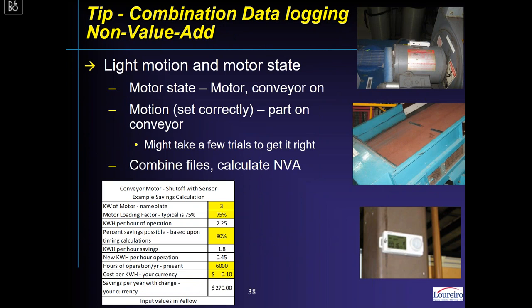One of the things we like to do is combined data logging to figure out value-add. On a grinder, a motor on/off logger showed that motor loading doesn't change much whether there's product on the grinder or not. Then we added a motion logger to see when there was actually product going through — someone has to manually walk over and dump it on the conveyor. By combining all that data we could calculate non-value-add: what's the savings from doing something smarter, like shutting the grinder down when there's no product on the conveyor?